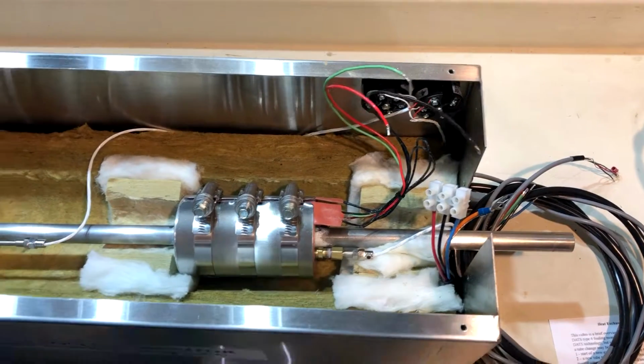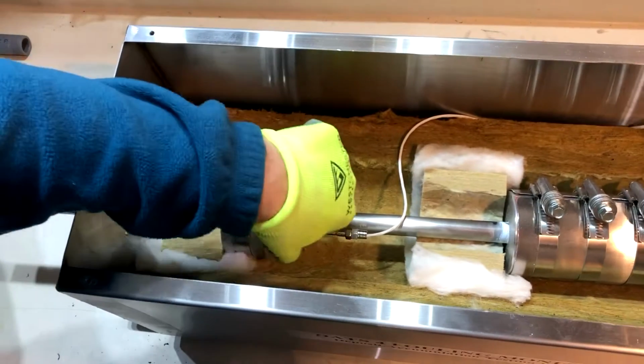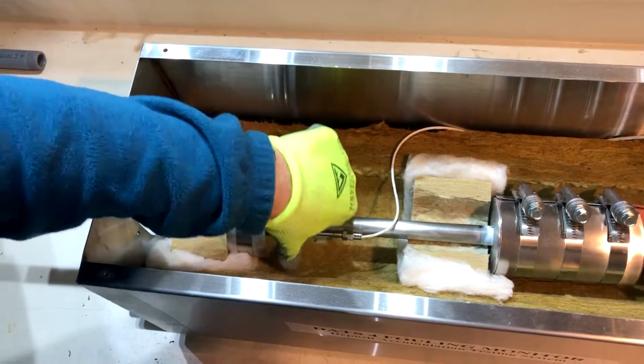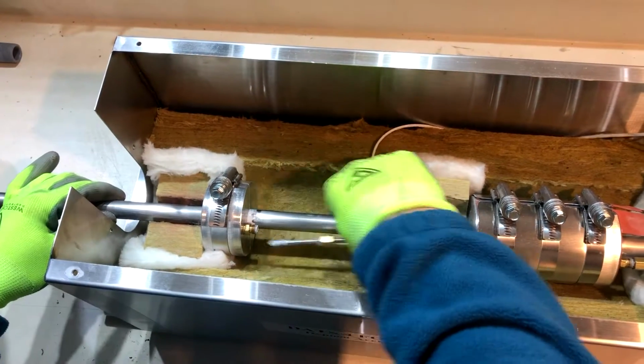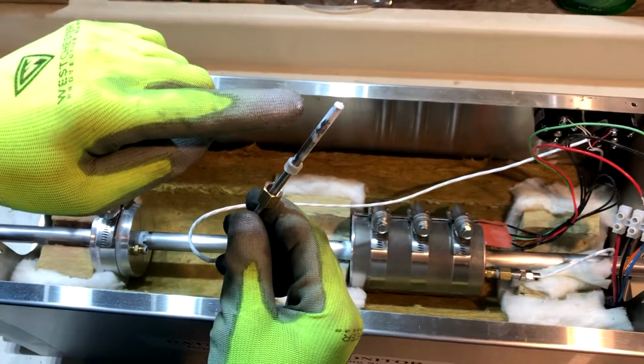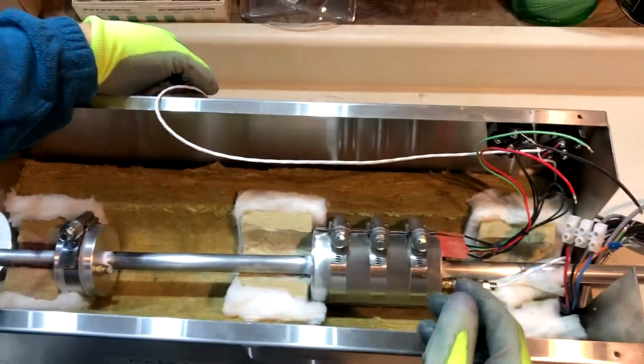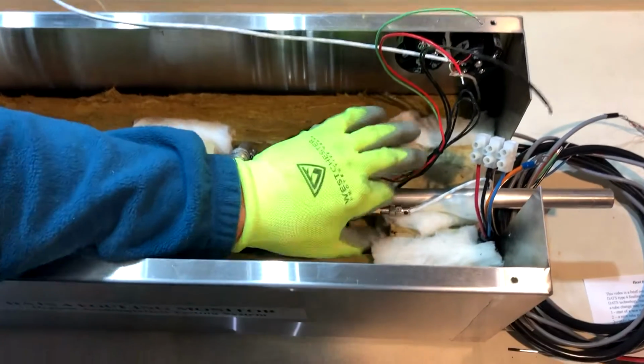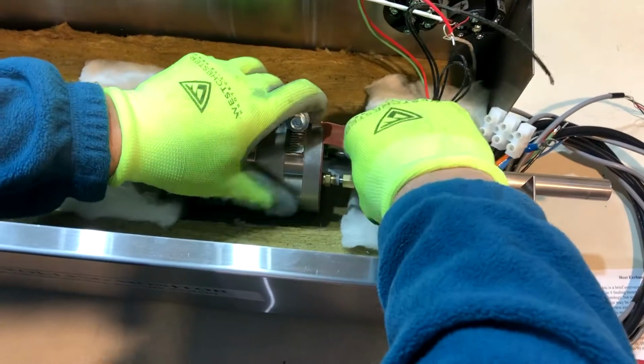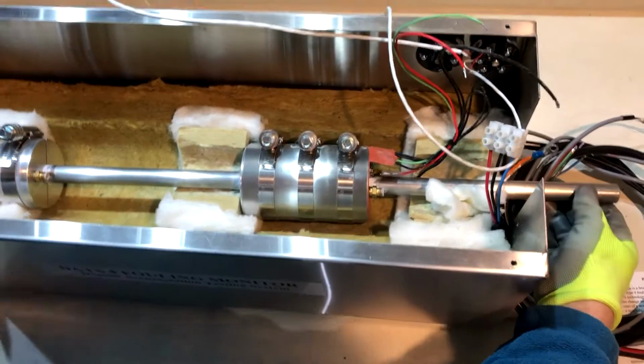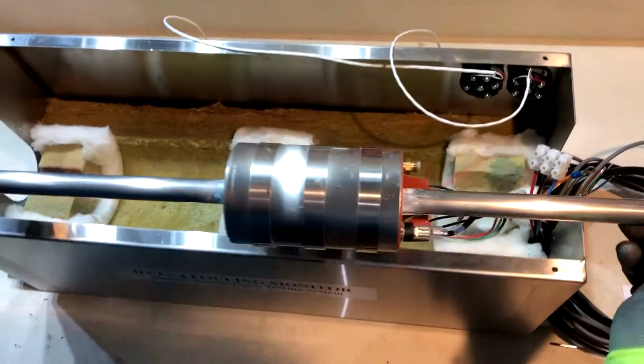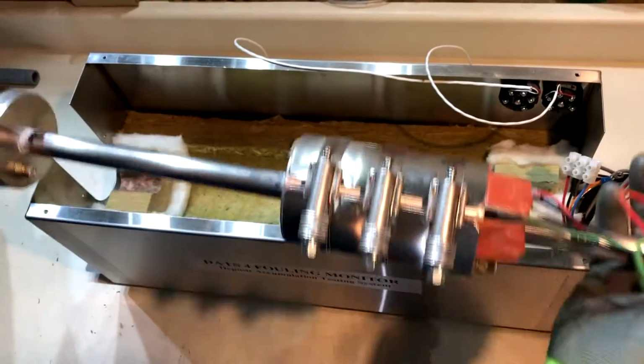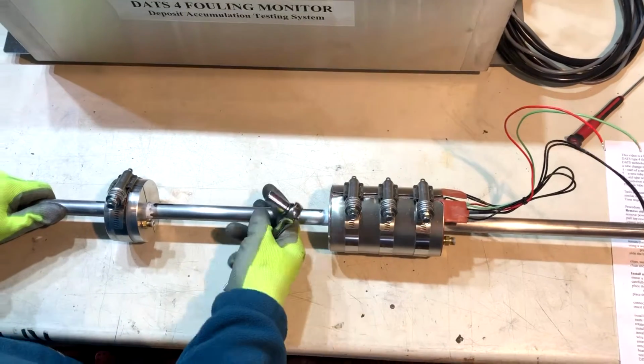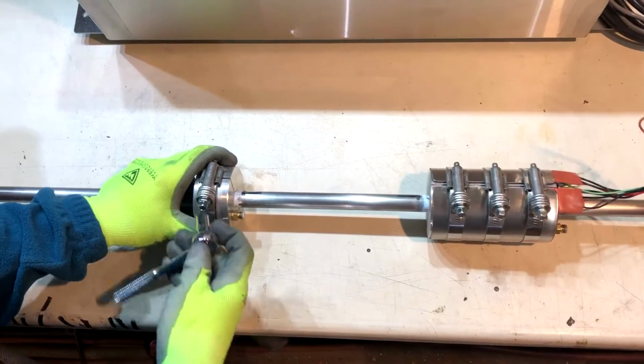So just by loosening these, get this disconnected. Now to remove the temperature sensors, just with thumb pressure should be all that's required. To loosen the connector, pull the temperature sensor out, and you'll notice the white thermal grease on the end of it. That's fine, just set it to one side. The same with the block temperature sensor. And it should, with a little bit of friction, pull out. Again, set it to one side. Now with those removed, you're able to lift the entire heat exchanger core out of the heat exchanger box, and you have it loose.